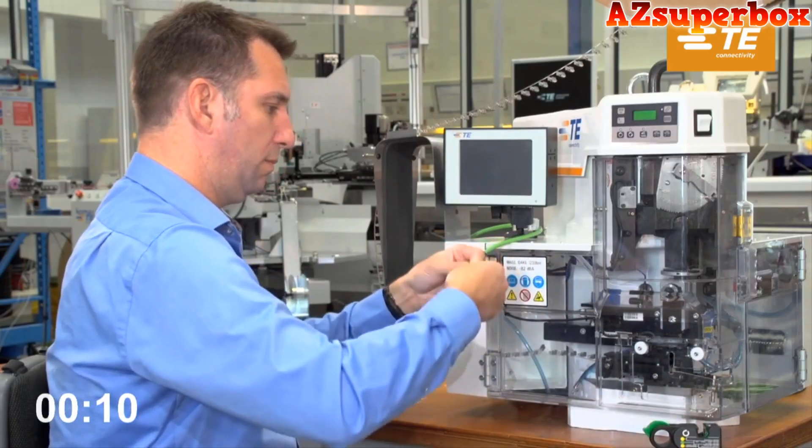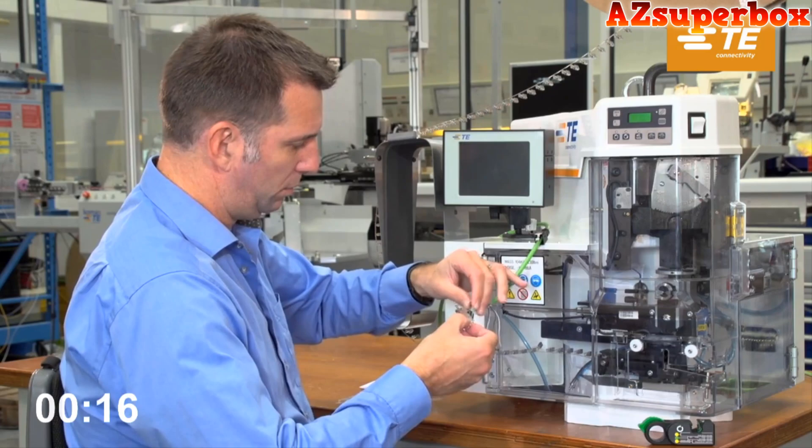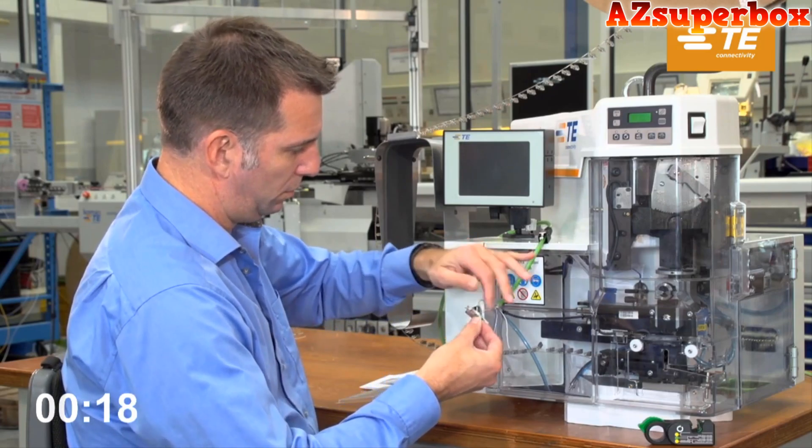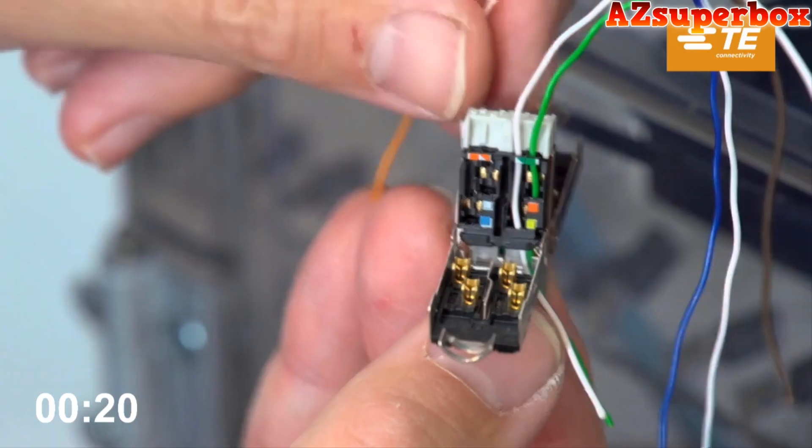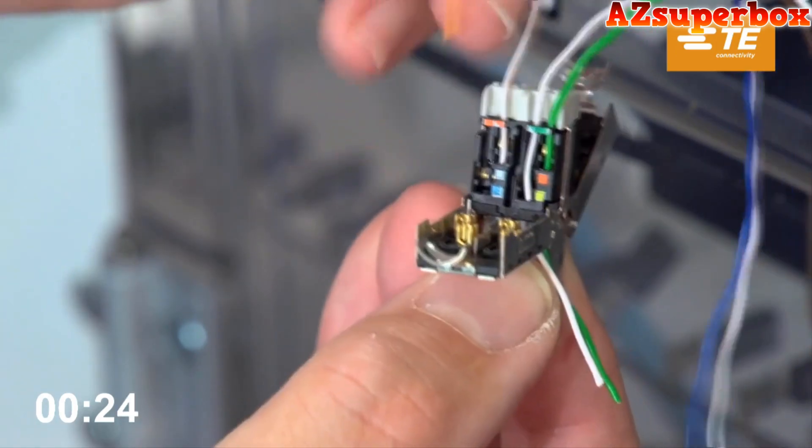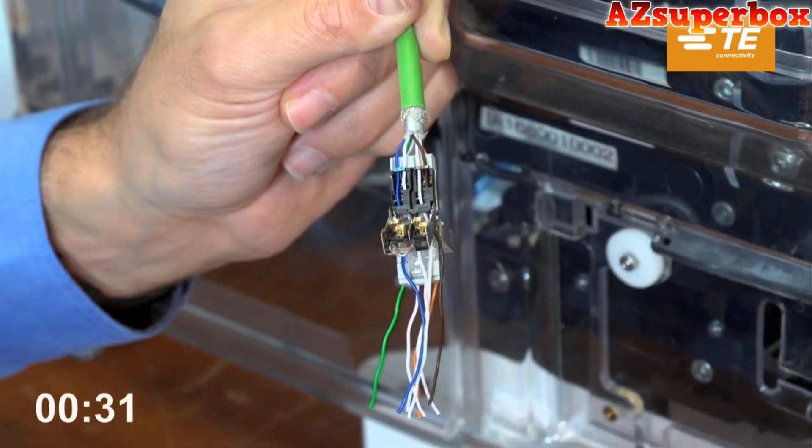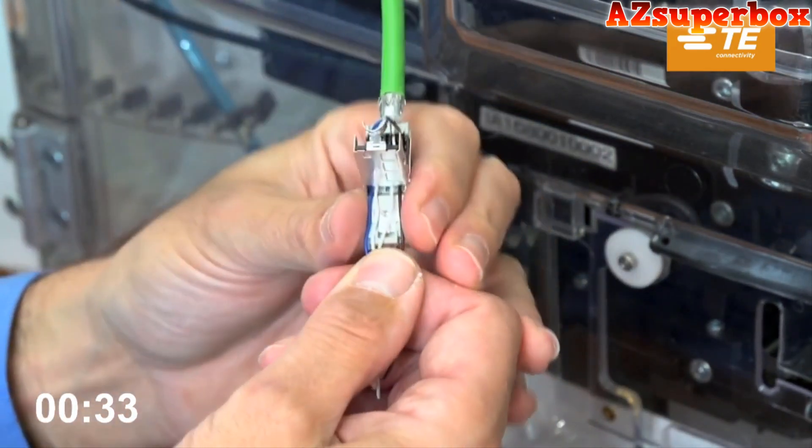Strip about 60mm of the outer jacket of the Ethernet cable, keeping 5mm of the braid intact. Straighten the wires and insert them into the cable manager according to the color coding. All commonly used Ethernet cables with wire sizes ranging from AWG26 to AWG22, stranded and solid, have been tested and approved.